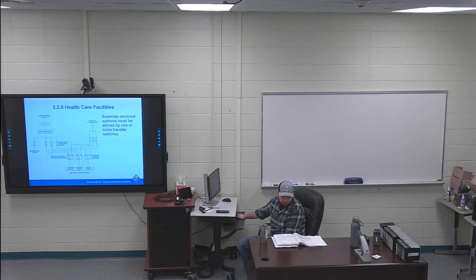Next page, page 23. The sentence before the first set of bullet points is highlighted. The life safety branch must supply power for the following. I keyed in hard on the first bullet point, lighting required for corridors. You gotta have lighting. Passageways, stairways, and landings at all exit doors. A lot of times these emergency lights, like this whole room, I got 9 lights in here. Sometimes the emergency lights is just enough for walkway lighting, so it might be like every 4th light has to come on in the emergency, just enough to be able to walk down corridors and stuff.